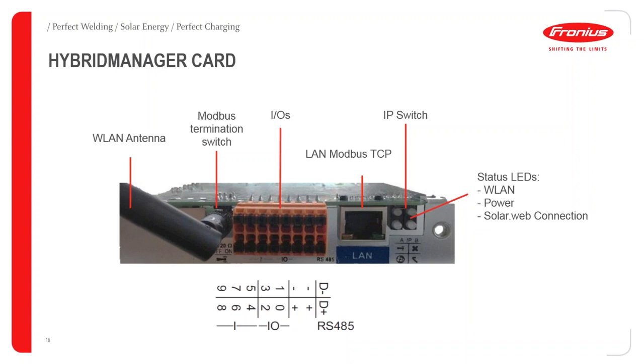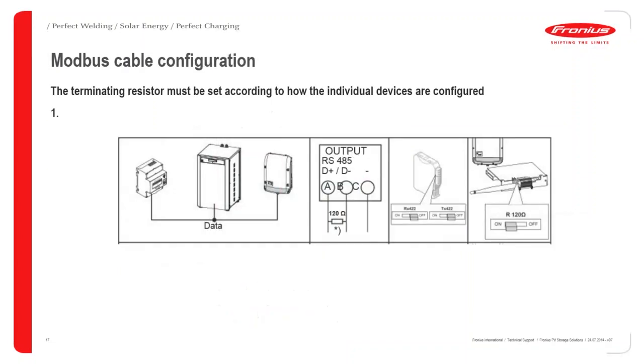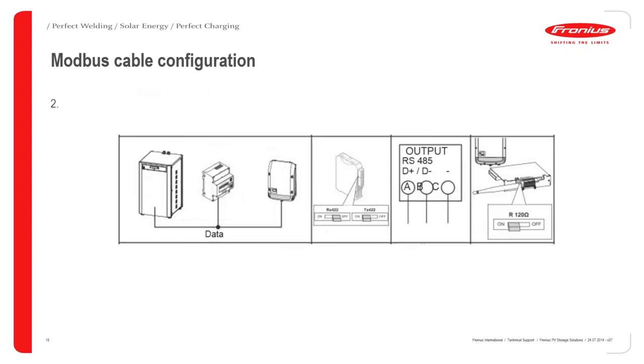Then you've got your I/O ports there. You can see the configuration down the bottom with your D minus and D plus for your Modbus ring, and then you've got other I/O ports there which can be configured for different situations. You've got your LAN port there, just like on the Datamanager, to be used for internet if you want to, and then you can also use Modbus TCP commands over that. And then you've got your IP switch like the normal Datamanager, that little white switch where the 4 LEDs are. So the status LEDs on this: you've got your WLAN, so your wireless, you've got your power, which is the tick, and then your Solarweb connection, which is the globe. So the cross doesn't get used on this one because there is no internal SolarNet ring with the hybrid, so that one's not really getting used.